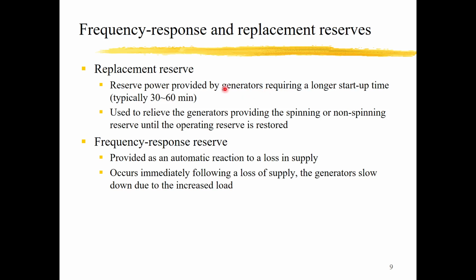Okay. And why do we call it replacement? It is used to relieve the generators from providing the spinning or non-spinning reserve until the operating reserve is restored. Okay, and then this is the fastest one. The fastest one is the frequency response reserve, and it is provided as an automatic reaction. It requires no human to intervene in the operation, because it needs a very fast response. So it should be an automatic reaction to a loss of supply, and it occurs immediately following the loss of supply, when the generators will slow down due to the increase of load.